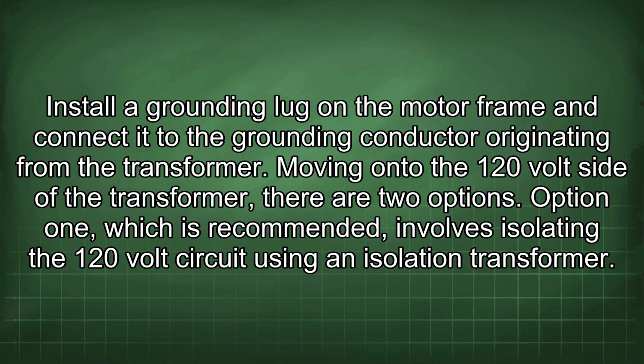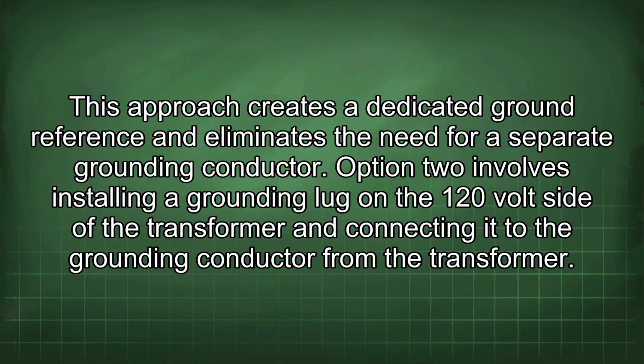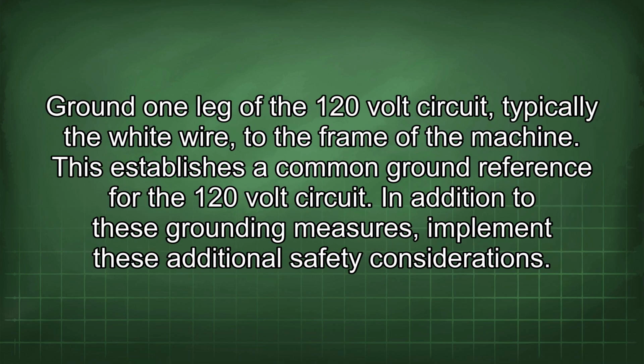Moving on to the 120-volt side of the transformer, there are two options. Option 1, which is recommended, involves isolating the 120-volt circuit using an isolation transformer. This approach creates a dedicated ground reference and eliminates the need for a separate grounding conductor. Option 2 involves installing a grounding lug on the 120-volt side of the transformer and connecting it to the grounding conductor from the transformer. Ground one leg of the 120-volt circuit, typically the white wire, to the frame of the machine. This establishes a common ground reference for the 120-volt circuit.